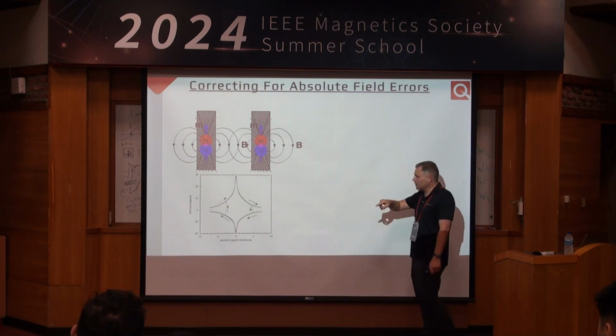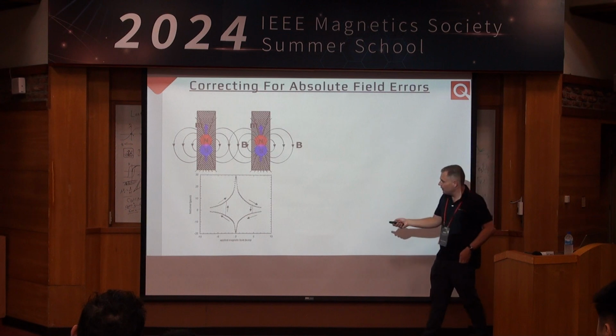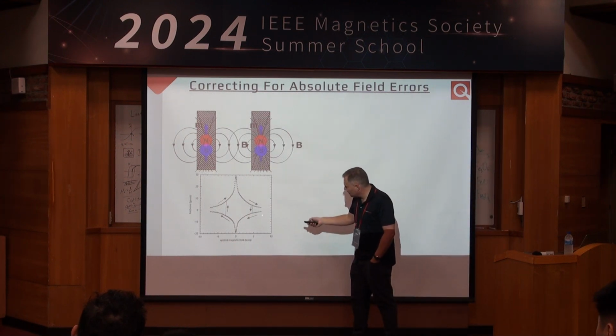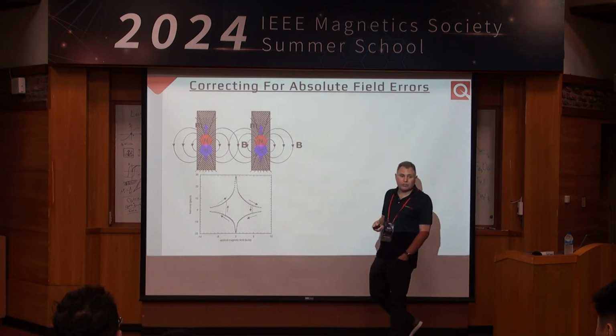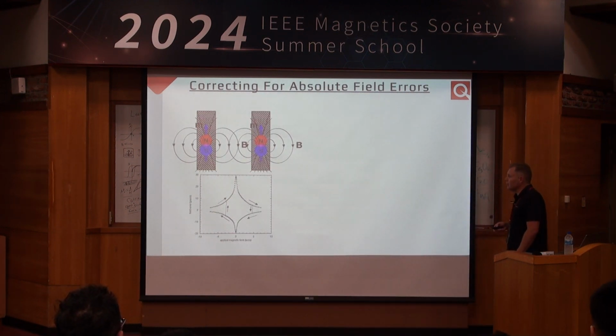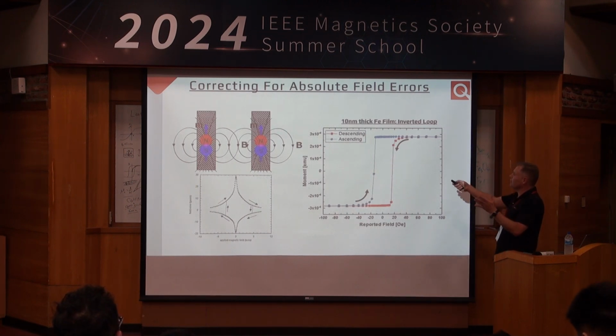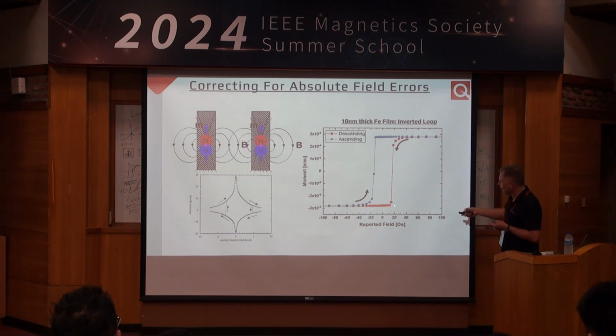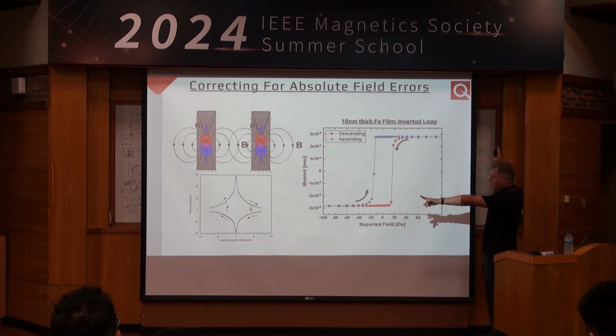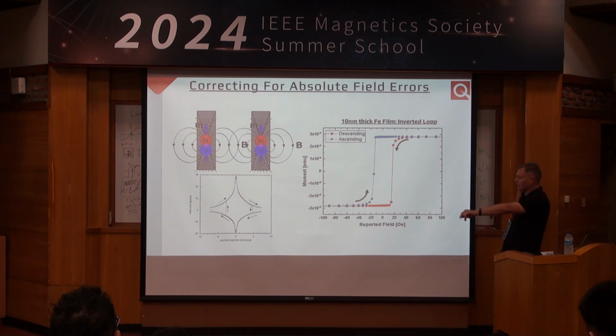remnant field. This is actually data from an MPMS-3, where again, they start off here at 7 Tesla, and this is the field error, coming back down to 0. Field error is on the order of 20 Oersted or so. How does this manifest in a measurement? So this here is a very benign measurement, a 10 nanometer thick iron film. And what we show here is we come from the descending branch shown in red, it flips on the positive side. It comes back, and then the ascending branch comes up and it flips on the negative side. And I should also mention that this loop actually went all the way out to plus minus 2 Tesla, which is zoomed in here on the low field response.